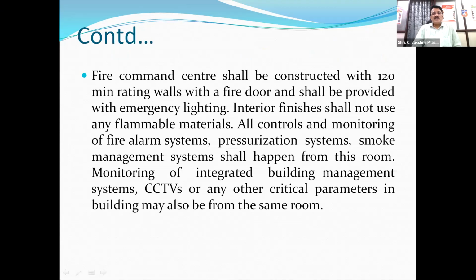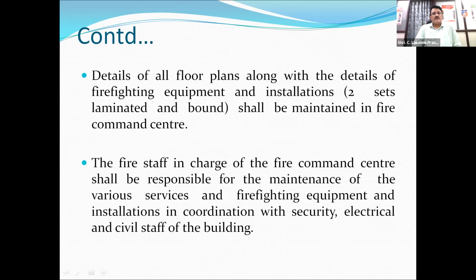Then it should also have CCTVs and other critical parameters of the building management system. It should contain the floor plans of the building with the firefighting equipment that is available in the building. All that should be indicated. When the fire personnel come to the fire command control room, they should be able to know what fire safety systems are available in the building, where the exits are located, and how they are protected. All that information should be available in the fire command center.